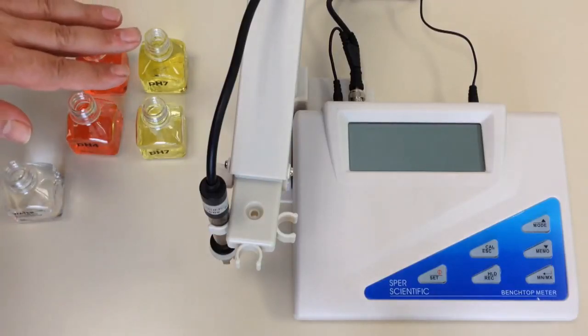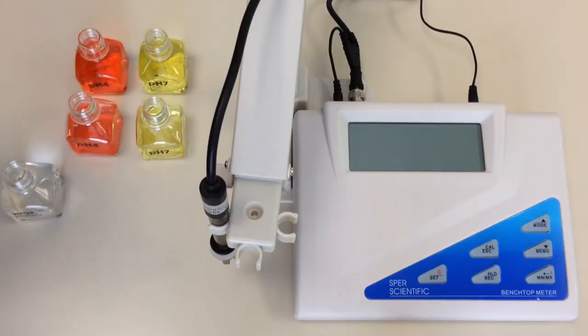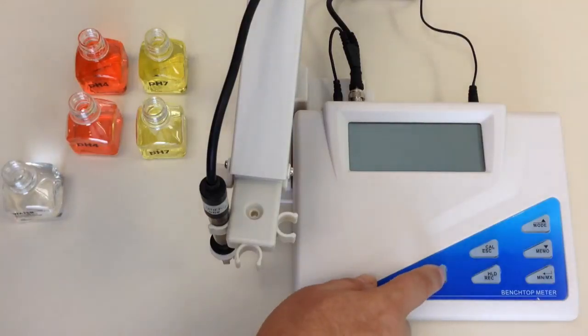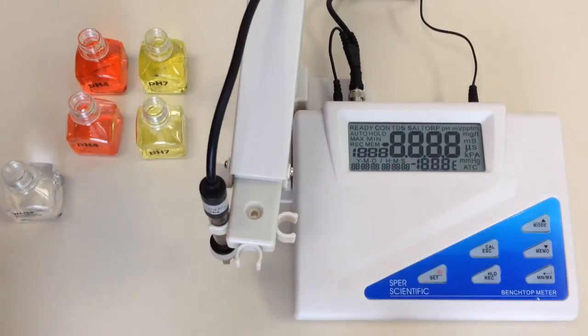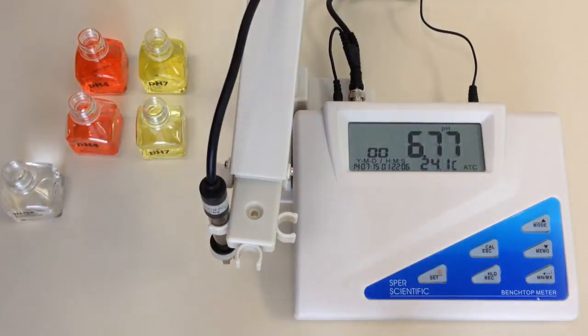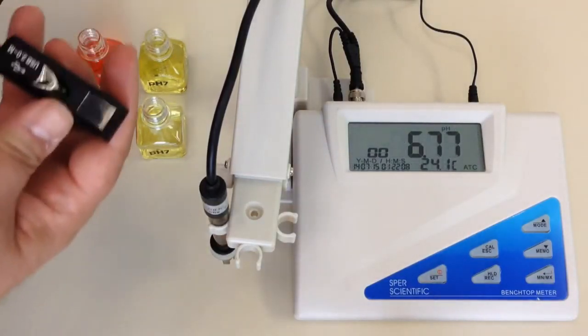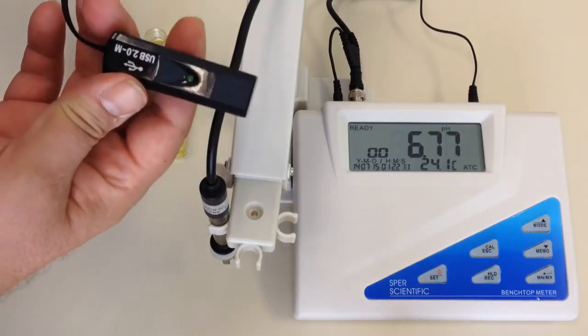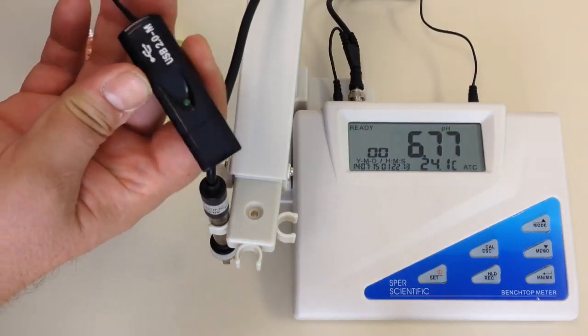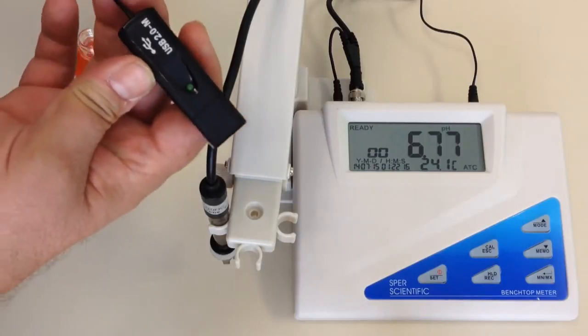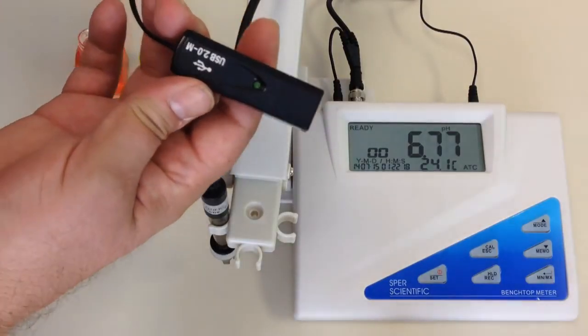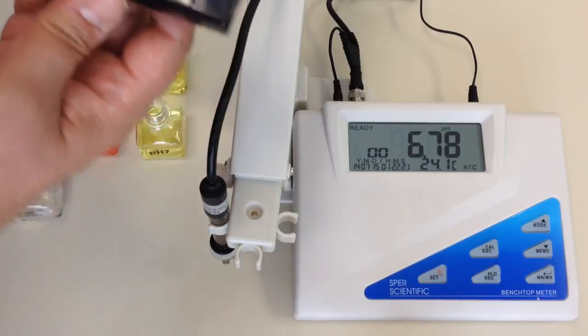We are also using standard buffer solutions, and if you're using NIST buffer solutions, please pay note to how we change the different features on this benchtop meter. Now, of course, the first thing you'd always have to do is make sure the unit is plugged in and turned on. One of the nice features of this particular benchtop meter is the ability to connect to your computer using a very simple USB port and connection. It comes with the software and everything that you need to do to connect this benchtop meter to your computer.